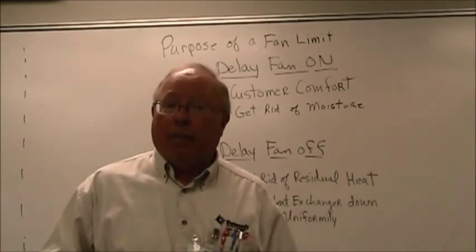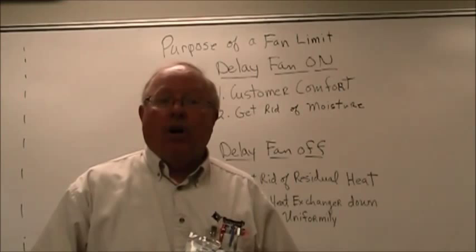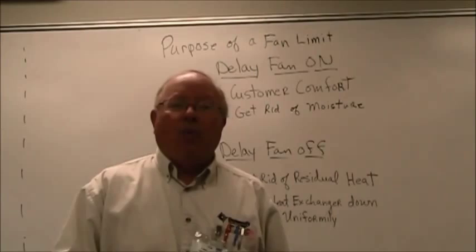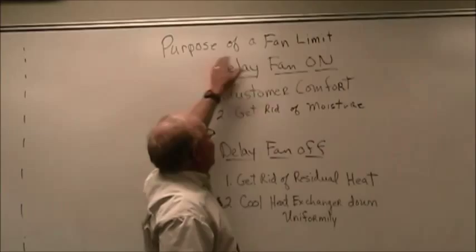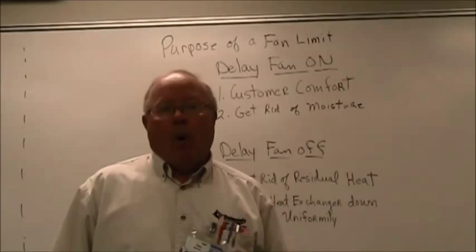Now you have to circulate air around the house in order to warm the house up. But we want to do it in a way in which the customer is going to be comfortable and in a way which is going to be efficient, in order to get rid of all the heat out of the furnace and to transfer it properly and with a lot of efficiency. So why do we delay the fan on? Why do we delay it off? The purpose of a fan limit control is to delay the fan on and delay the fan off in the heating cycle. That's its job.